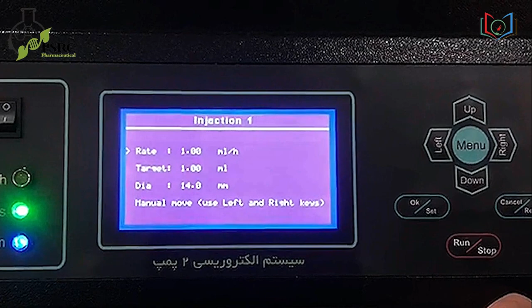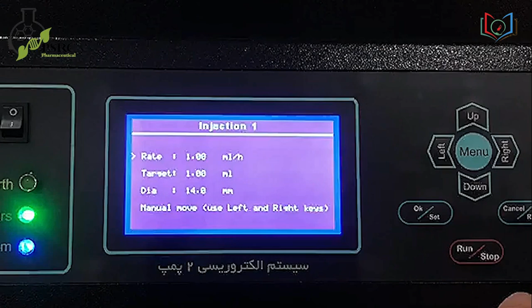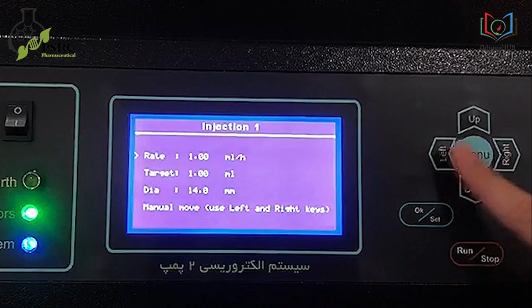As you can see, we have the injection, scan, and distance settings for each pump. Here, by pressing the menu button on each part, you can set all related details. In set injection 1, you can adjust the injection rate. In this device, you can set it from 100 microliters to 250 milliliters per hour. The amount of solution in the syringe or target depends on your syringe volume, your required quantity of fiber, and syringe diameter that could be measured by calipers. In the manual move, by pressing left or right, you can check needle blockings.